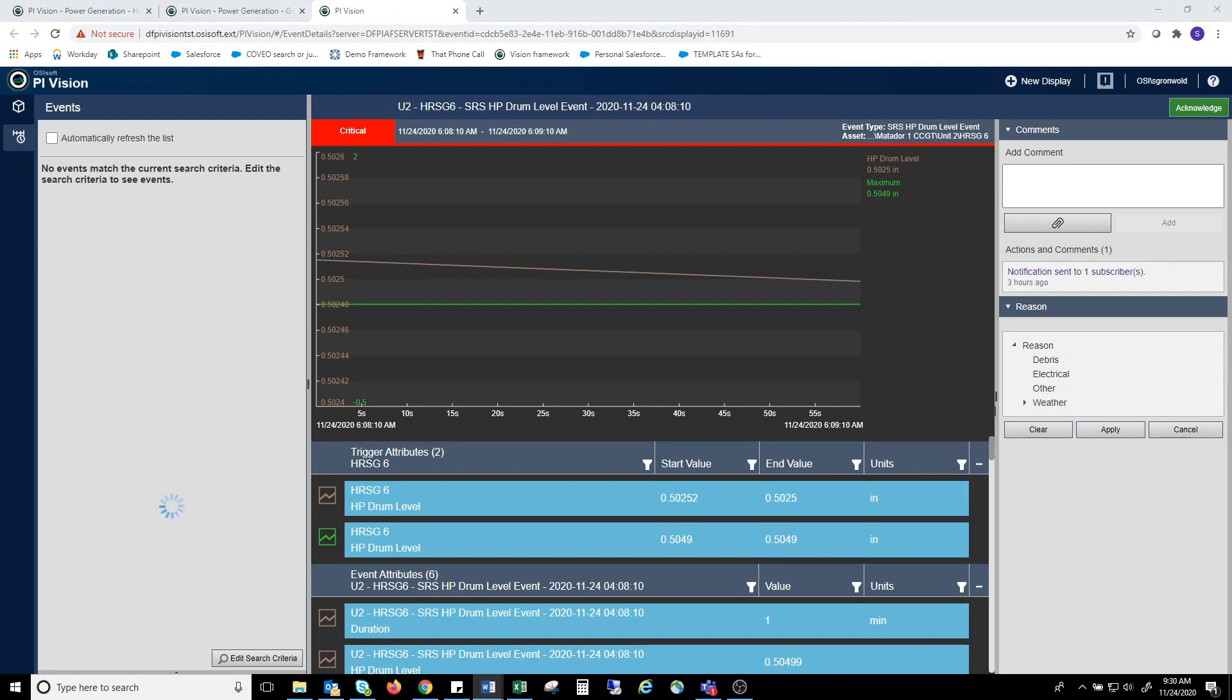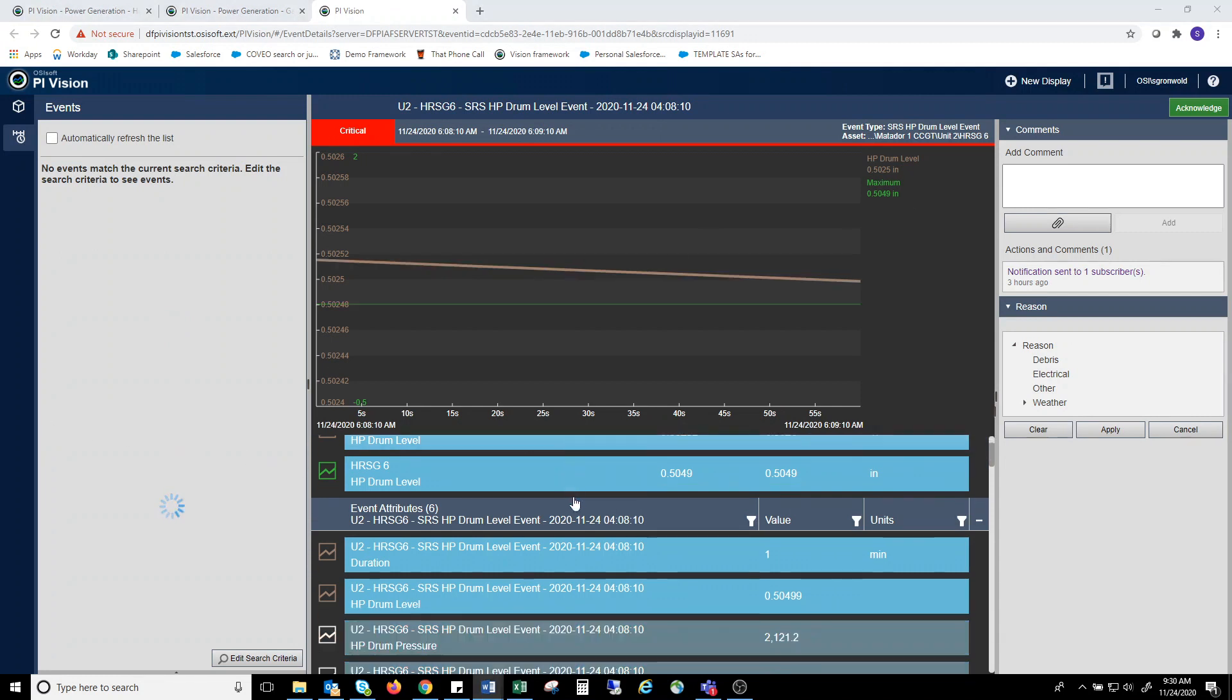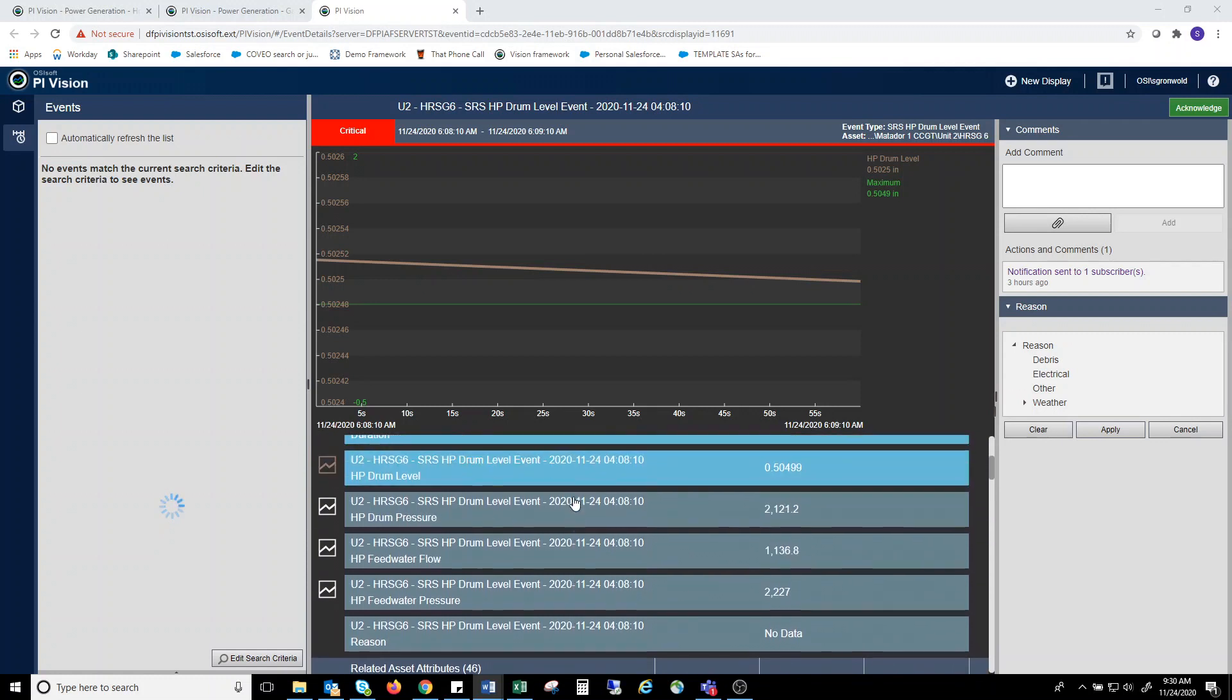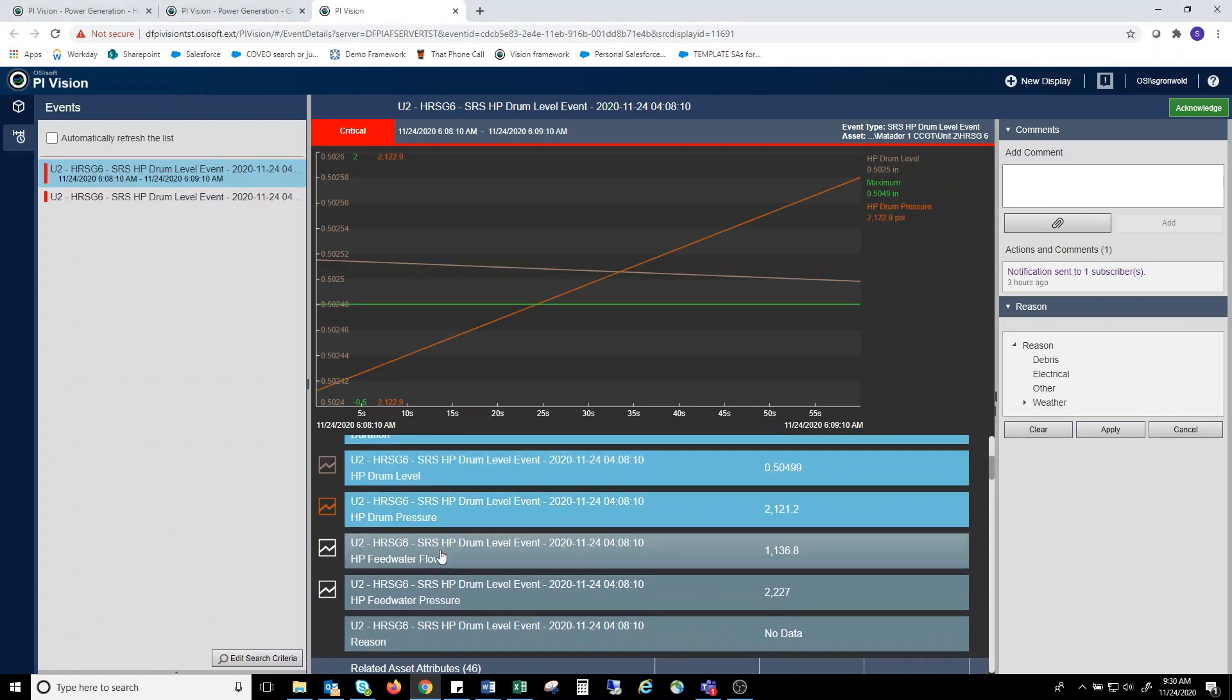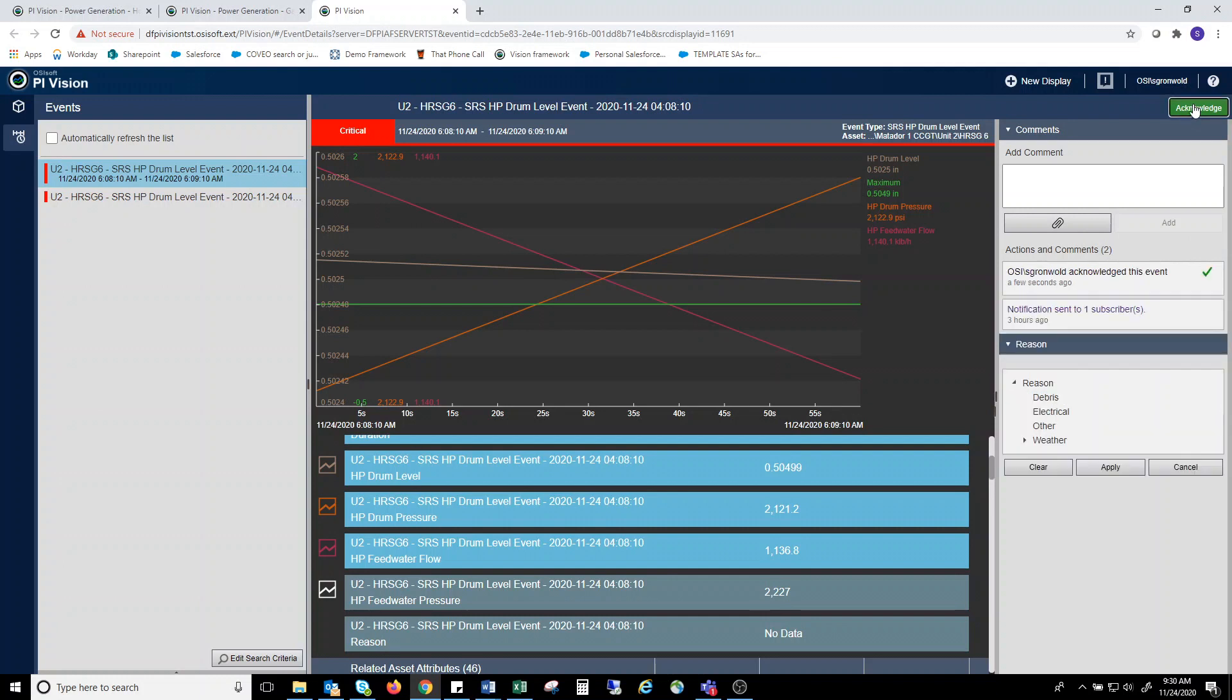An engineer coming in to look at root cause can add a couple of other parameters, let's say drum pressure and feed water flow to help them do some diagnosis. The engineer can acknowledge the event, showing that it has been looked at. You can also add a comment to help classify the cause of this event.